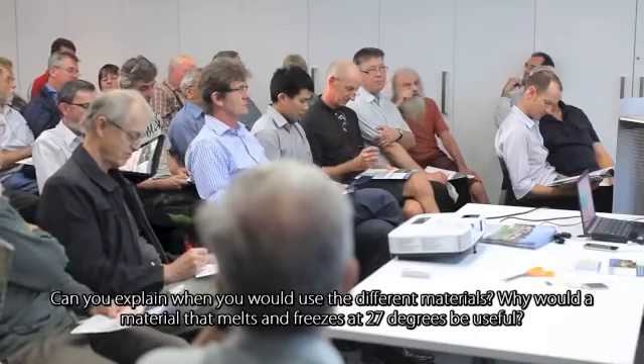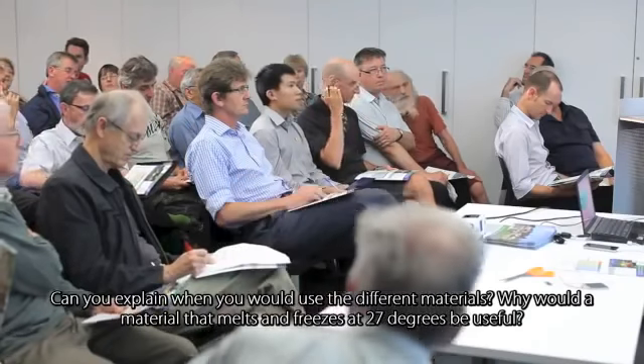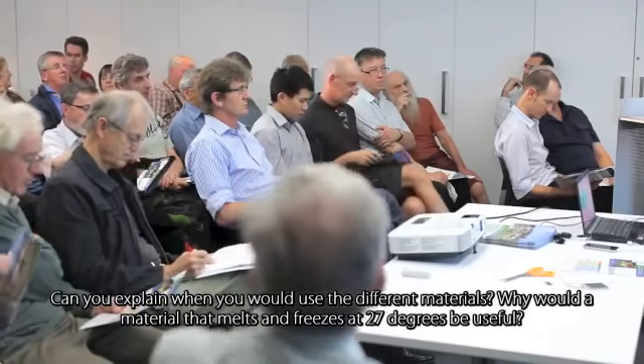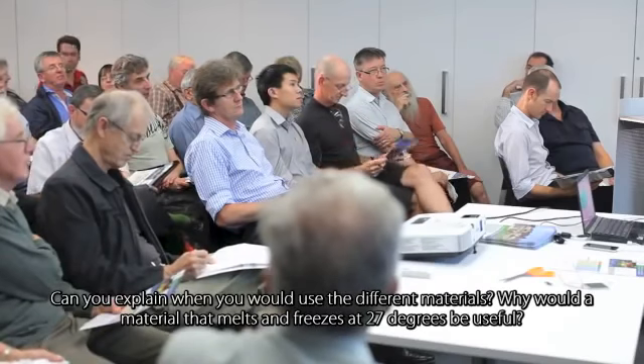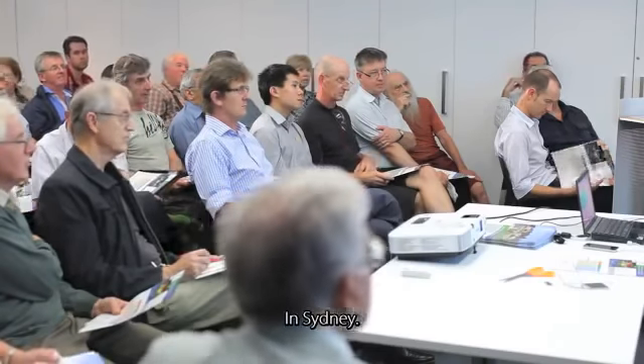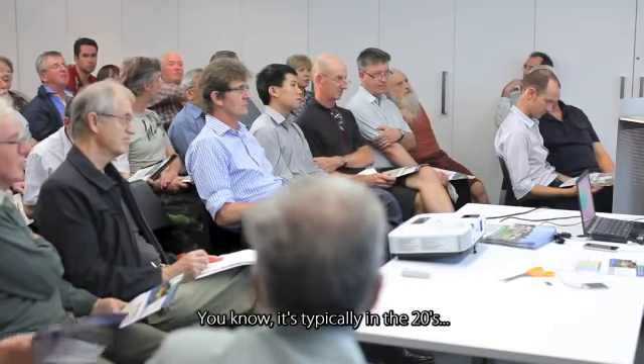Can you explain when you would use the different materials? Like, why would a material that melts and freezes at 27 degrees be useful? Where do you live? In Sydney. What's the weather like here? Well, typically it's in the 20s. Okay, so what about if you lived in Townsville? You mightn't get a night refreeze. So if you have a material that refreezes at a different point, you can refreeze it passively.